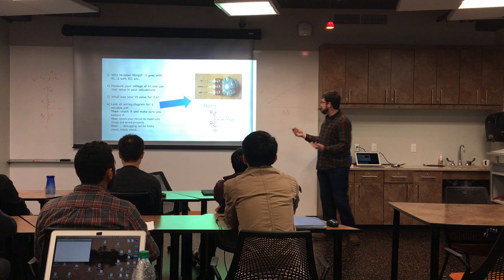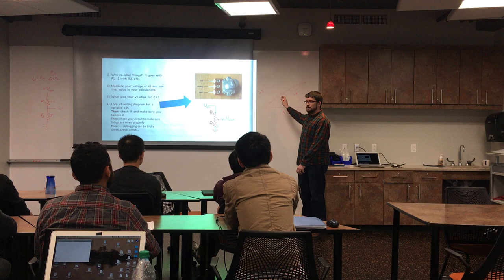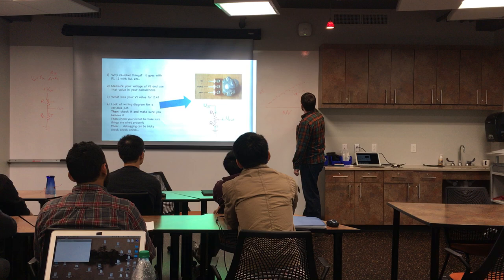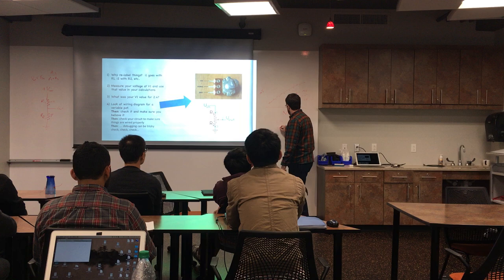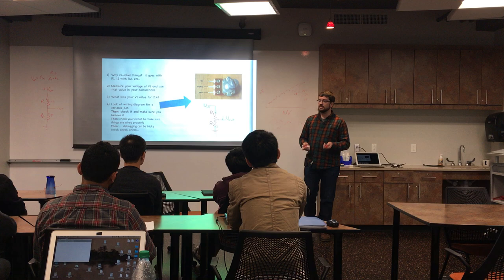Right, so millivolts per kilonewton. Several people took that calibration factor, multiplied it by how many millivolts they measured, and successfully created a unit of millivolts squared per kilonewton as an output, which is not at all what you want. So remember, you have to take the reciprocal of that, so you would have kilonewtons per millivolt times millivolts, and that would give you the amount of kilonewtons that you had on your load cell. So that was a pretty common mistake that several people made.